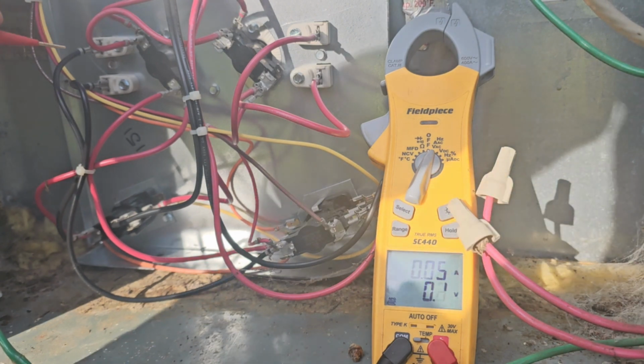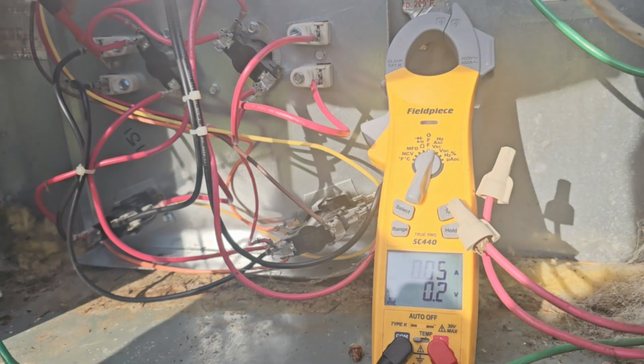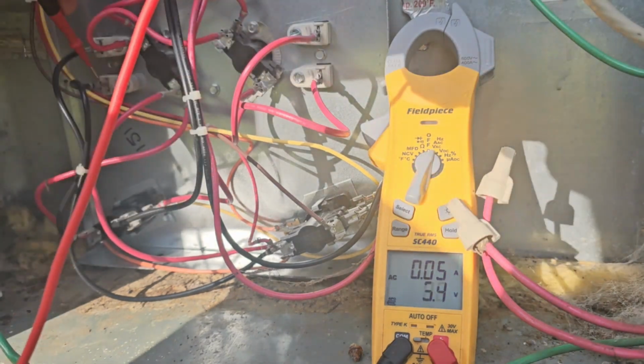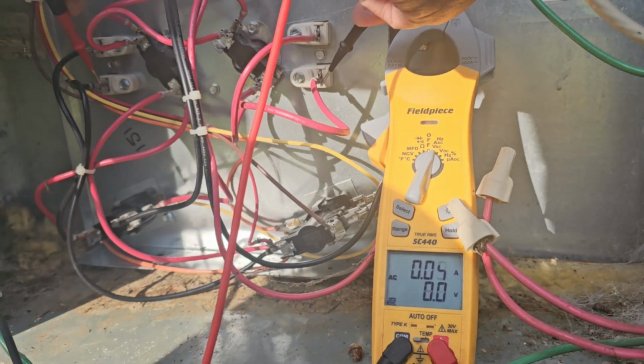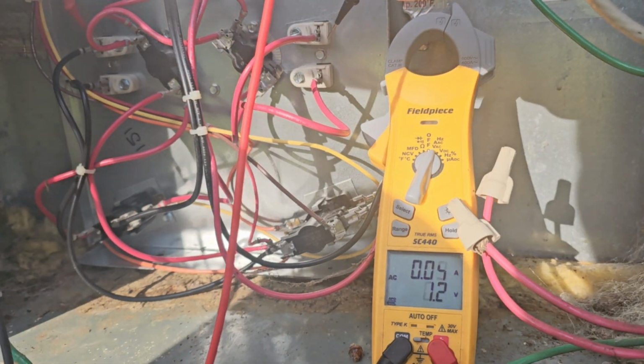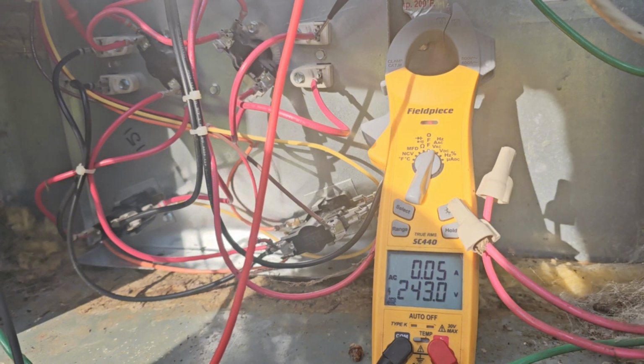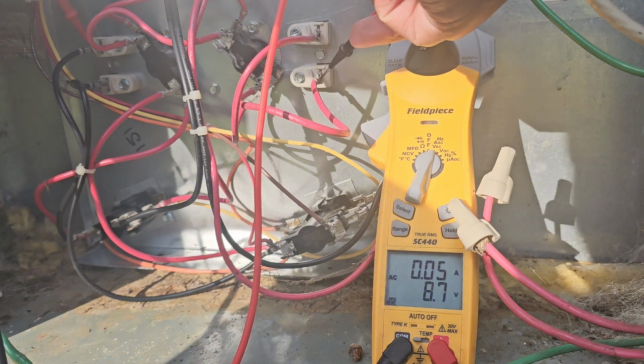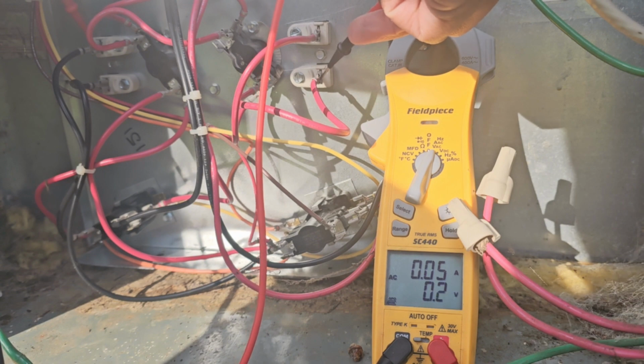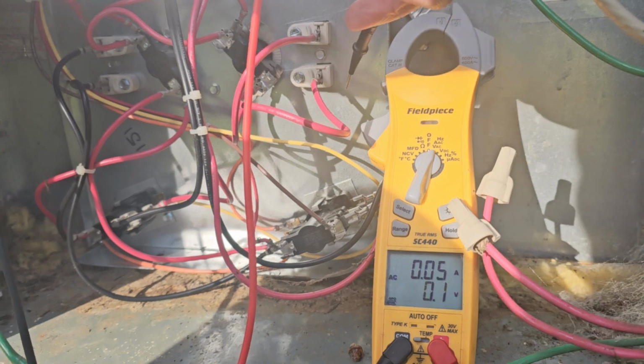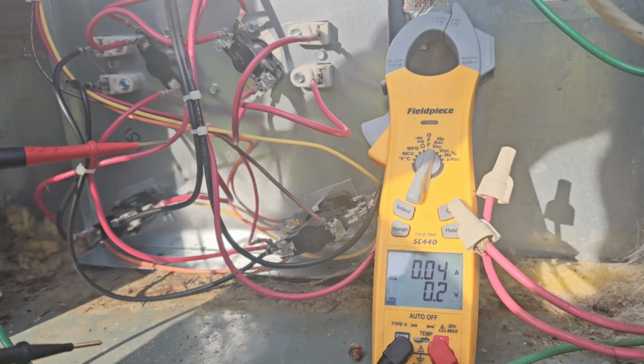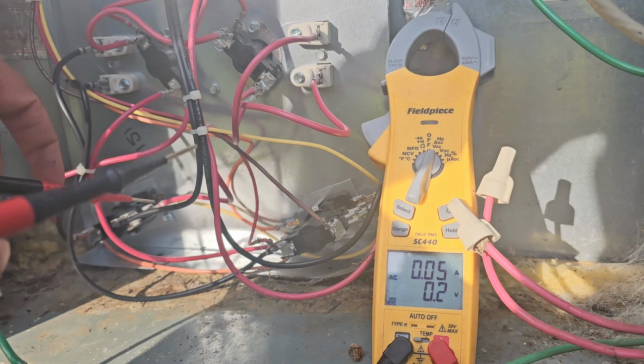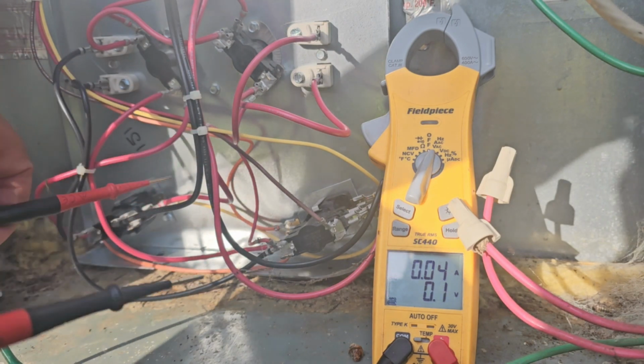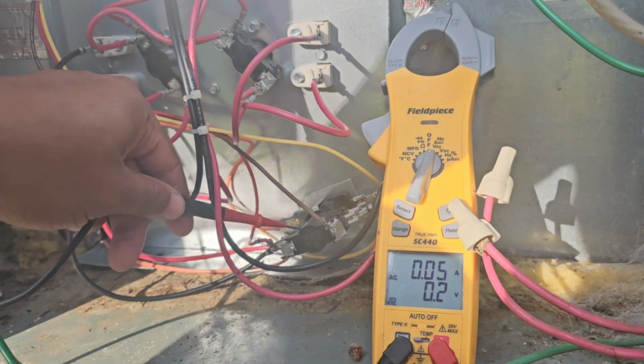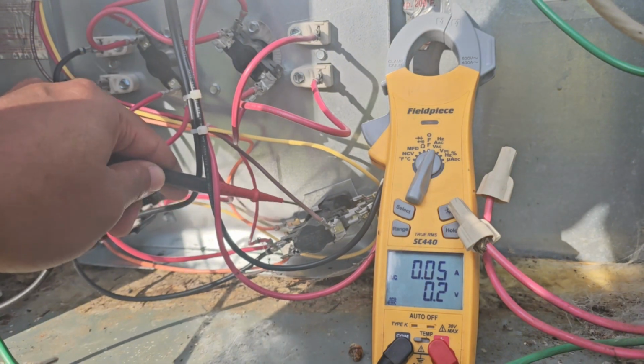If I check from here to here, I have zero. Up top, 240. If I go from here to here, it's zero volts as well, like they're the same leg of power. The only thing I can trace it back to where something doesn't make sense is on this sequencer.